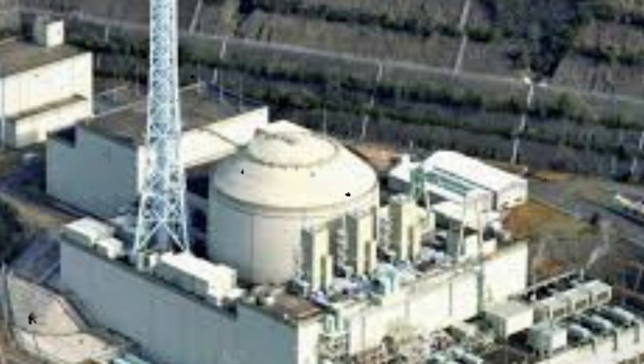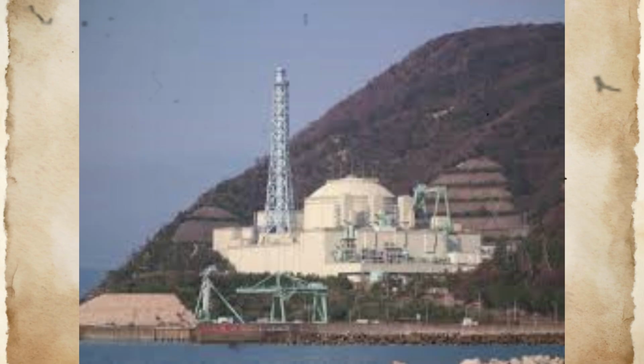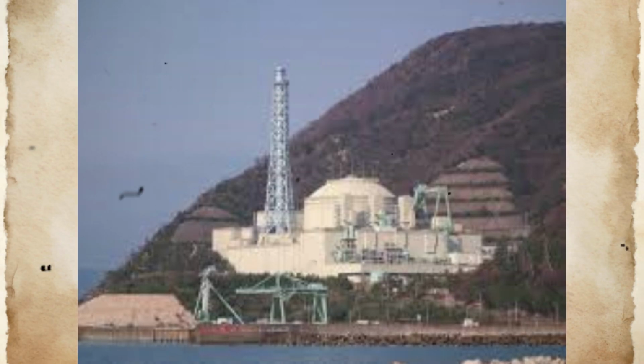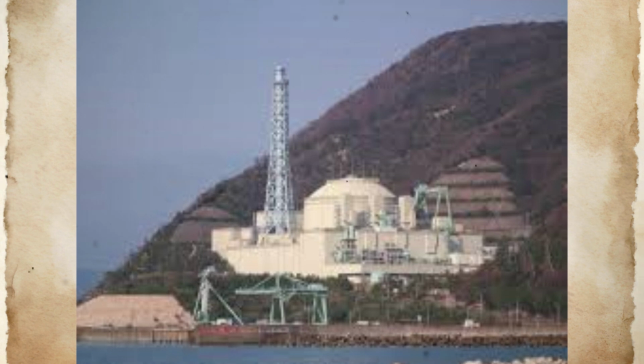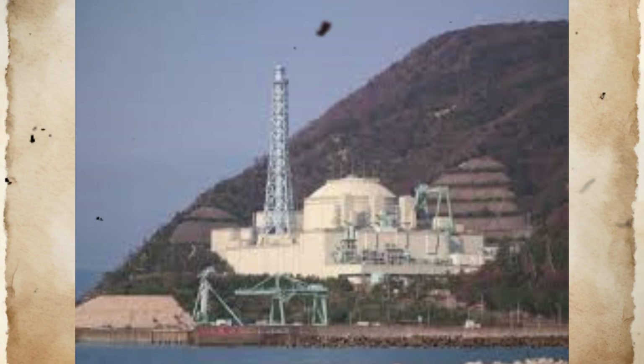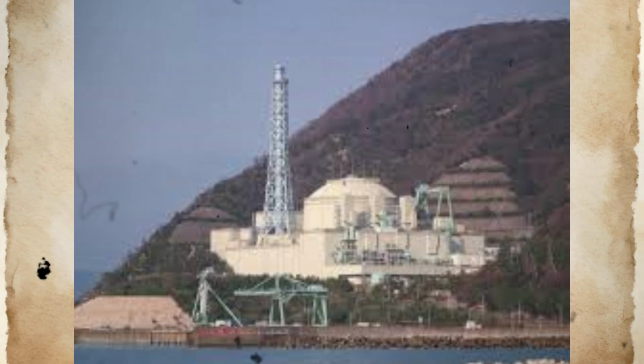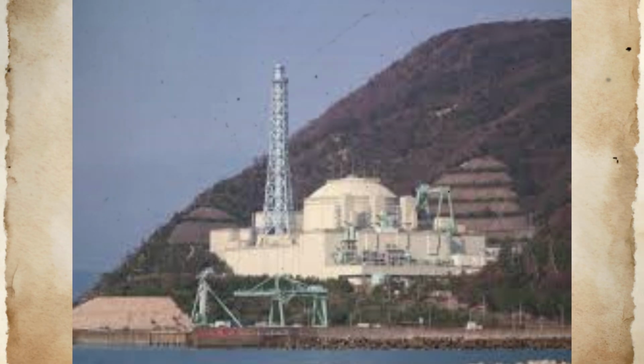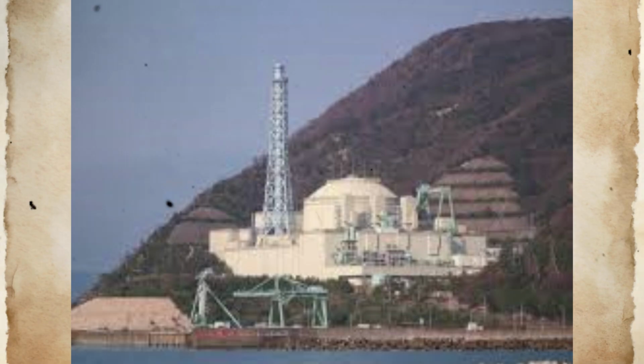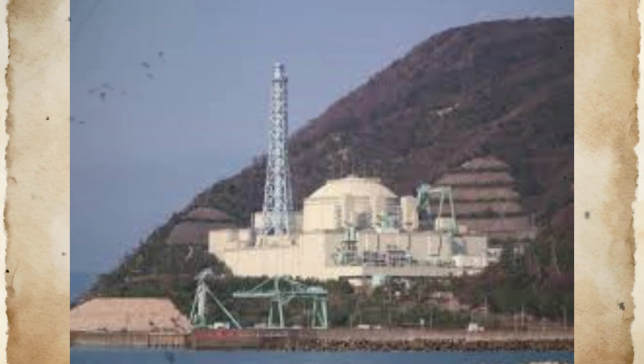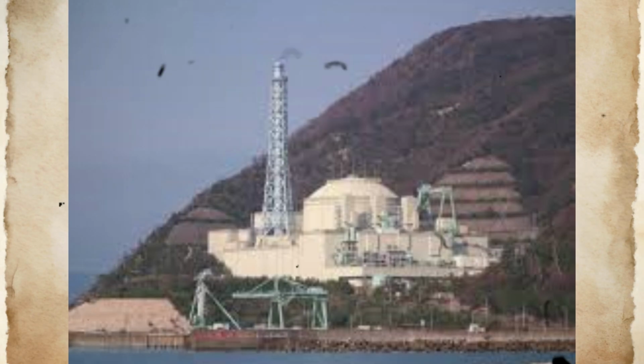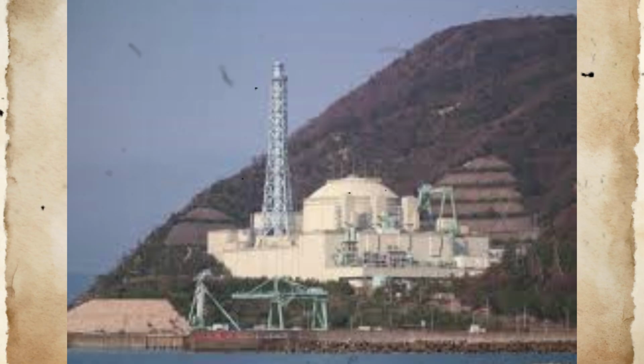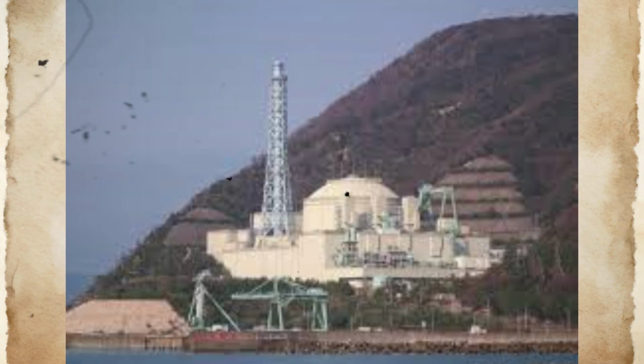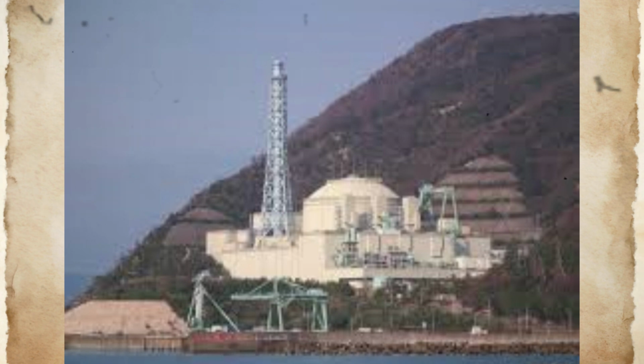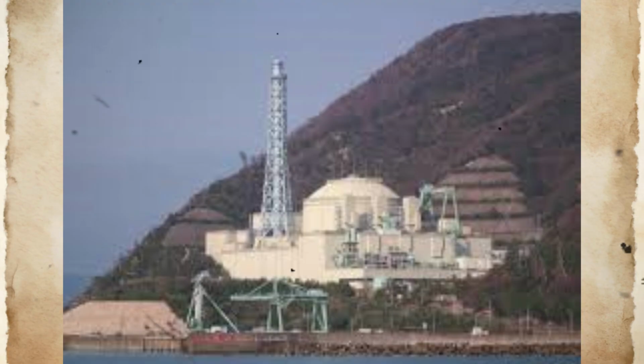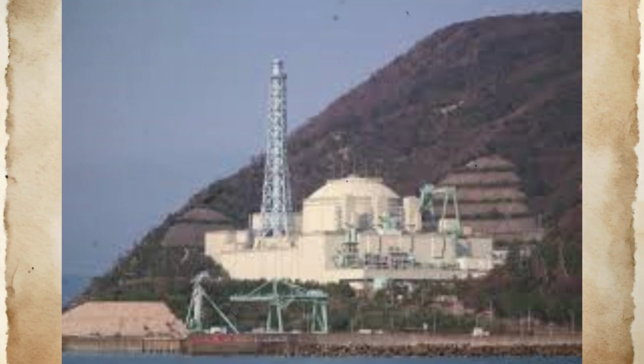Following the manual reactor trip at 2120 on December 8, 1995, Monju operators faced the challenge of maintaining adequate decay heat removal while isolating the failed component in SHTS Loop C. The reactor shutdown had eliminated active power generation, but substantial decay heat continued to be produced by fission product decay within the reactor core. This thermal load required continuous cooling to prevent core overheating, creating operational constraints that influenced every subsequent decision. Decay heat levels immediately following shutdown from 43% power operation totaled approximately 3% of full thermal power, representing roughly 20 megawatts of heat generation that required removal through the plant heat transport systems.